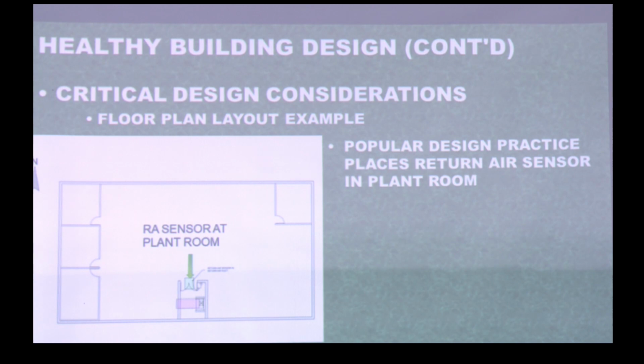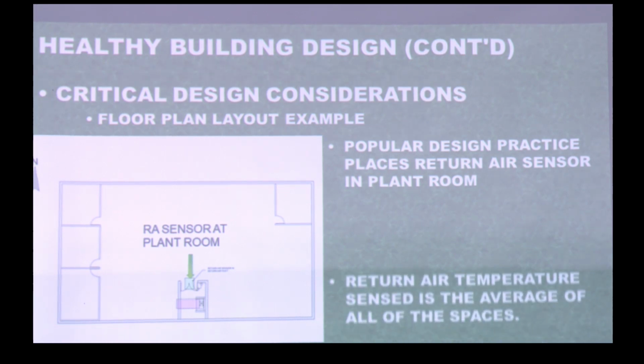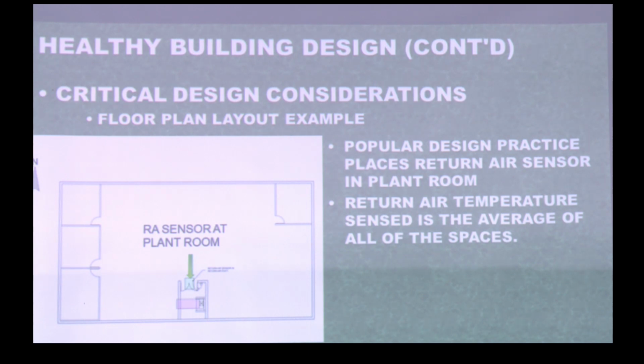So here's the example that I'm referring to. Popular design practice has the sensor back at the return air duct in the plant room. So we're sensing the average of all the temperatures of all the spaces, internal spaces, external spaces. That's coming back at maybe, call it 70, 72 degrees Fahrenheit or 22. So this building is orientated northwest. The east-west axis is the long axis of the building. Sun rises in the morning. You've got the heat load on the eastern side of the building.